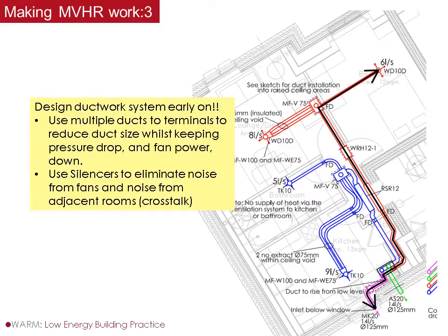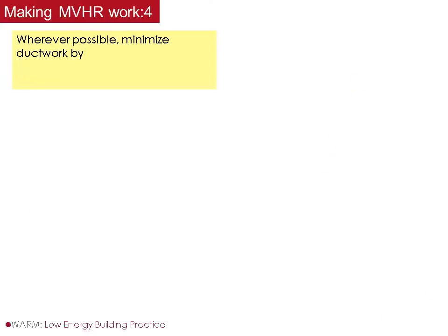You also need to be careful because you can get crosstalk, which means you need to lay out to allow for noise going up one duct and along, and not coming out to another room, so you can't hear what's going on in the other room. So you need to pay attention to the ductwork layout and design very early on, because silencers tend to be quite chunky, and ductwork is chunky. You need to get it designed, basically.